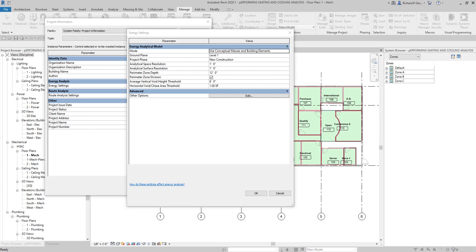You can always check the help file for Revit 2020. You also have the Average Vertical Void Height Threshold. This value is used to avoid the application of unwanted thermal loads and properties to analytical spaces like ceiling voids and small vertical spaces such as closets and small storage spaces. When an analytical space's average height falls within this threshold, it will automatically be assigned to unconditioned zone equipment. All analytical spaces assigned as unconditioned are not included in any systems analysis. The average vertical void height threshold is determined by dividing the volume by the area.